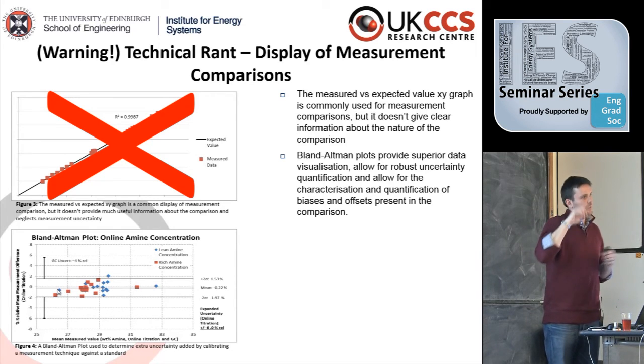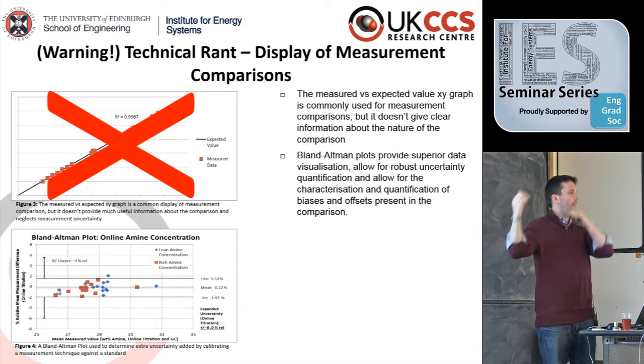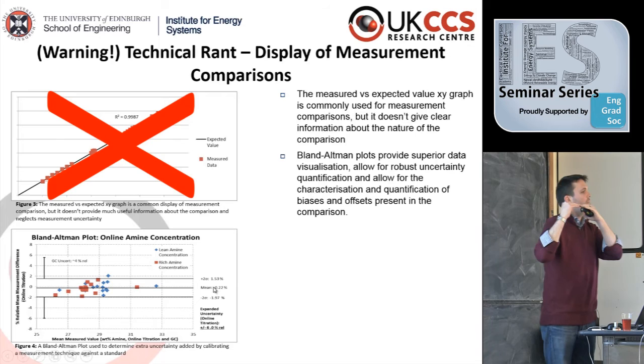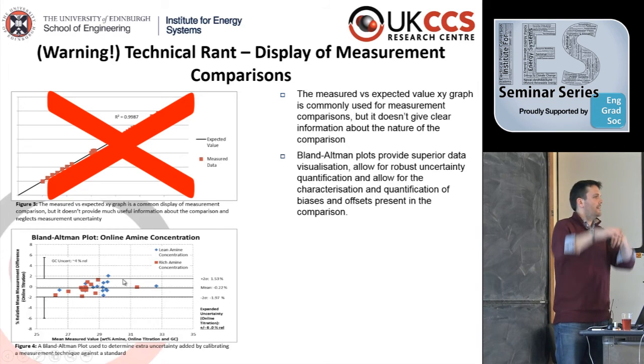So one of the clever things it can do is it can actually quantify for you the added uncertainty if you take a measurement and you go against the calibration. So like you have this calibrated set, and you've now taken this new measurement that you have and compare them. This thing can actually quantify the added uncertainty for you. So what it does here is I have this comparison. I know the uncertainty of one of the measurement sets, and the other one is a new one. So if you do all these comparisons, you can see that on average, the difference between them is 0. That's good. That means that it's random noise that we're talking about here. And then you can see what the distribution of the scatter is, add together the uncertainty, and you kind of have this new quantification. That's one of the things you can do.